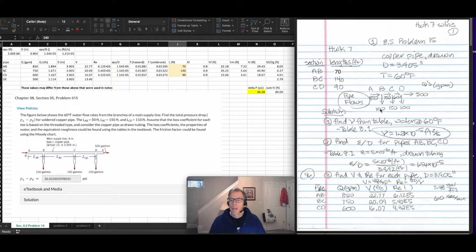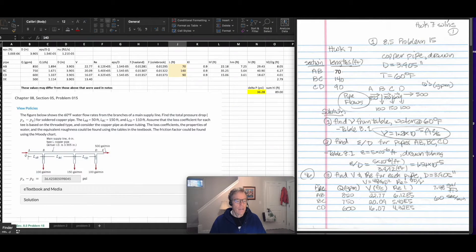I have the givens up here. The first thing I needed to do is calculate the pipe flows in all of the pipes. I used the steady-state incompressible continuity equation, given these three flows and the flow out the main line, to calculate the missing flows in each of the pipe sections. Step one was to look up from the tables in the textbook the kinematic viscosity for water at 60 degrees — 1.21 times 10 to the minus 5 feet squared per second.